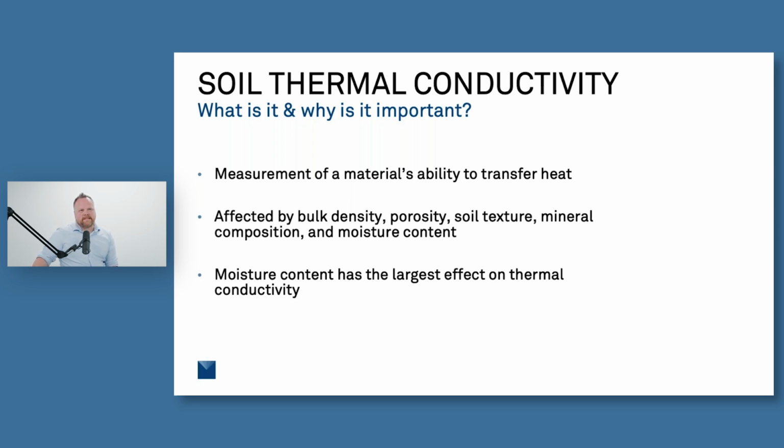But the thing that has by far the largest influence on thermal conductivity is the moisture content of the soil. Moisture, water in particular, is very good at transferring heat. So the more moisture content you have in a material, generally the higher that thermal conductivity is going to be.